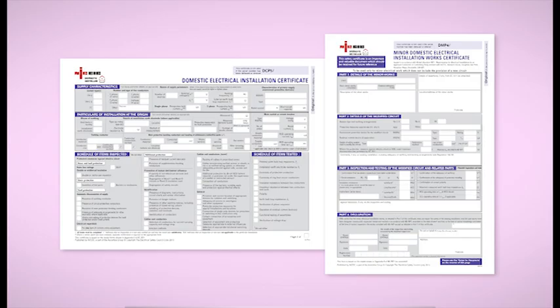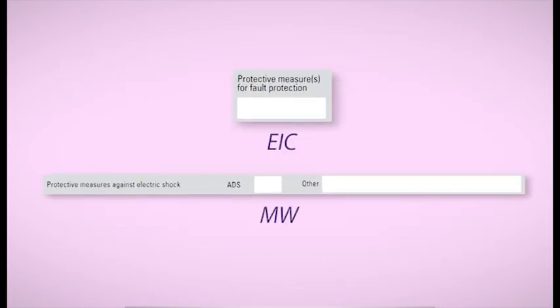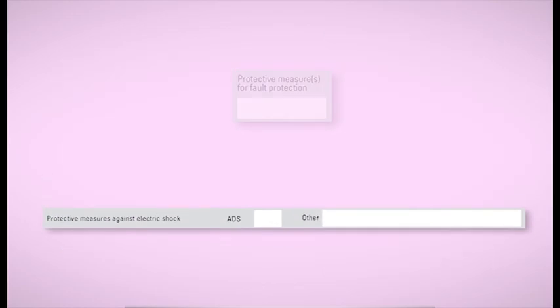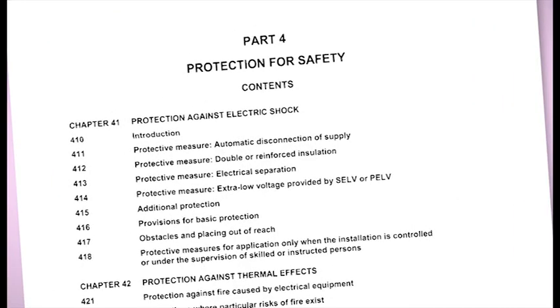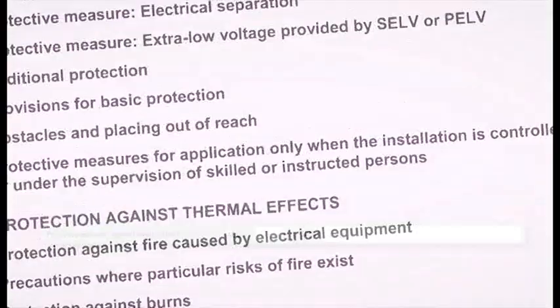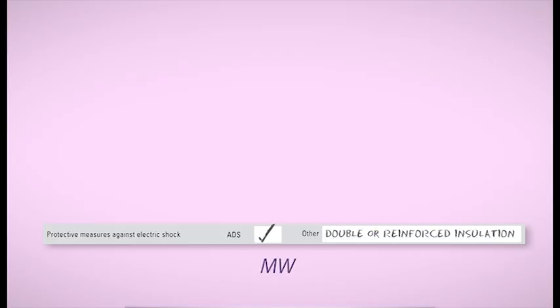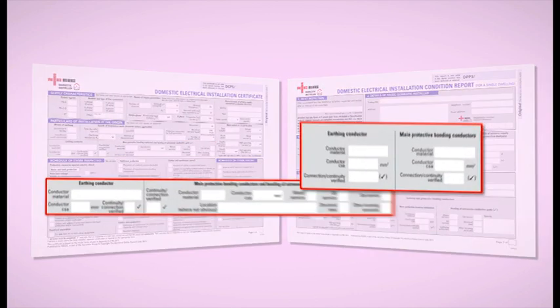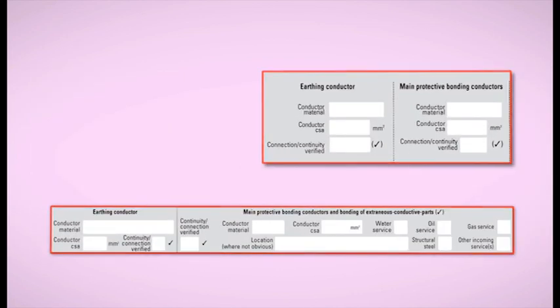The next box to examine on the certificates deals with protective measures for electric shock. Now this in most cases is automatic disconnection of supply, ADS, but can be followed by one or more of the protective measures detailed in Chapter 41 of the regs. So for example, double or reinforced insulation could be recorded for a circuit supplying a non-metallic hand dryer, which is a common example of equipment adopting this protective measure. Next, let's look at boxes referring to protective conductors. First, we have the earthing conductor.